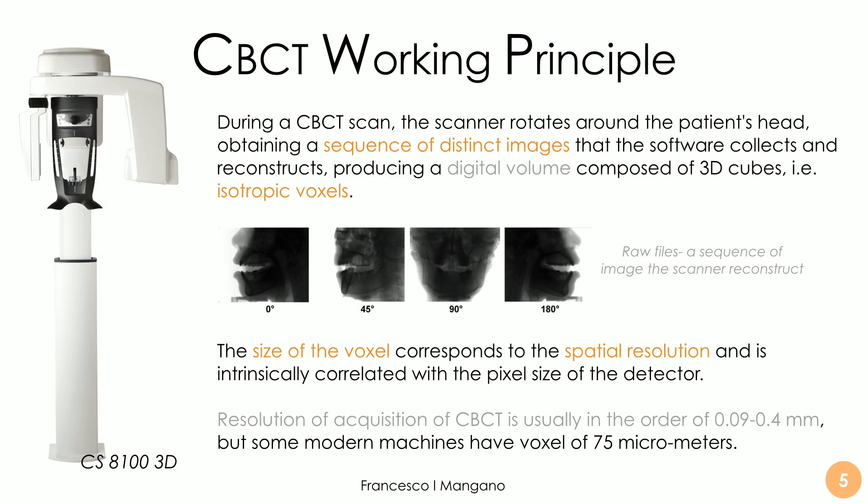During a CBCT scan, the scanner rotates around the patient's head, obtaining a sequence of distinct images. The software collects all these images and reconstructs them, producing a digital volume composed of 3D cubes called isotropic voxels. The size of the voxels basically corresponds to the spatial resolution, and it is intrinsically related to the pixel size of the detector.